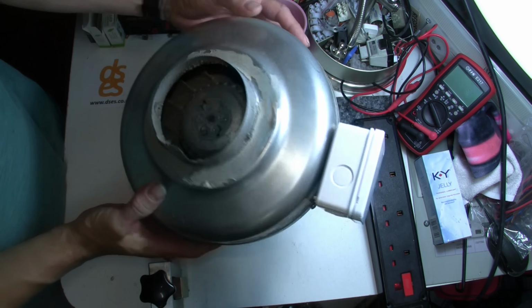I've waffled on about priority controllers before in my video about my gyro switchover unit that gives my electric shower physical priority over the EV charger to keep my maximum demand down, and although that's not quite the same as this, it's not friggin' far off. The main difference with the gyro is that it uses a current sensing relay, which means both loads get power, but it's only when the priority load starts taking more than about 10 amps does it mechanically switch over.